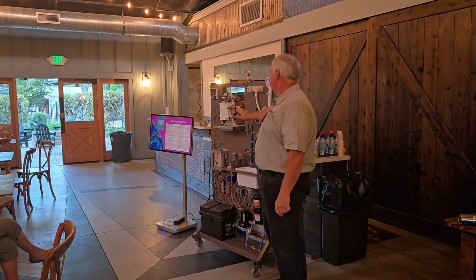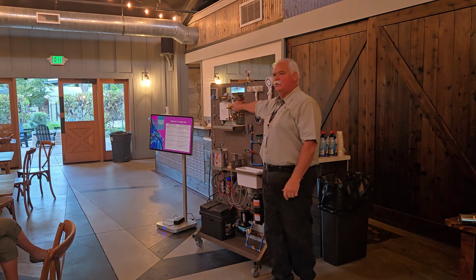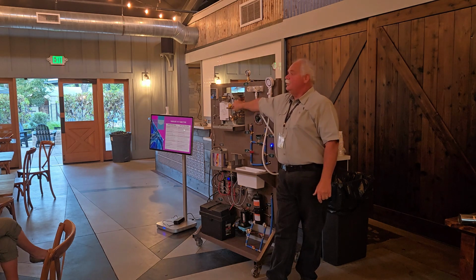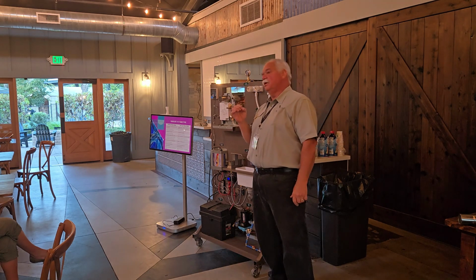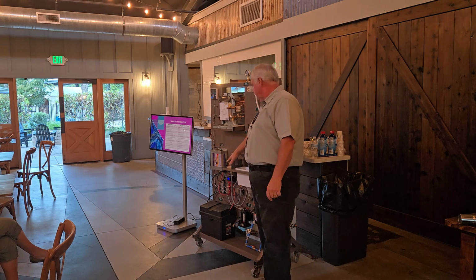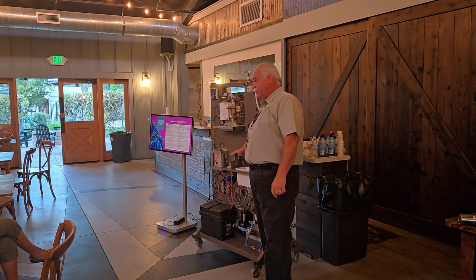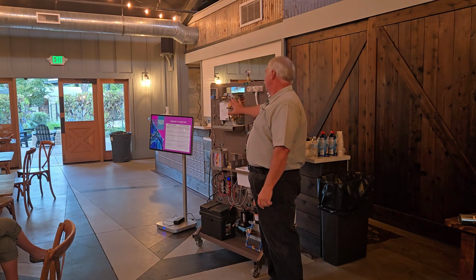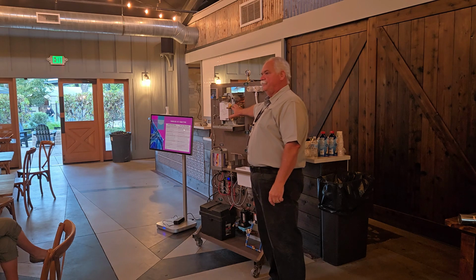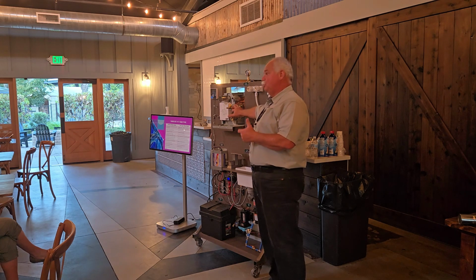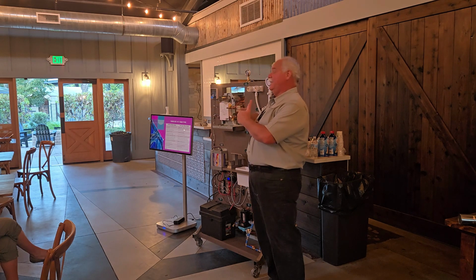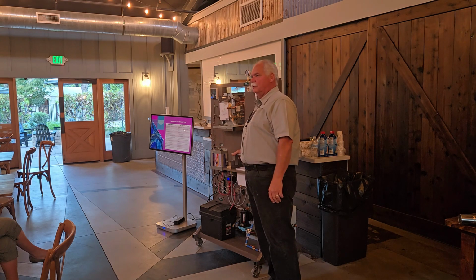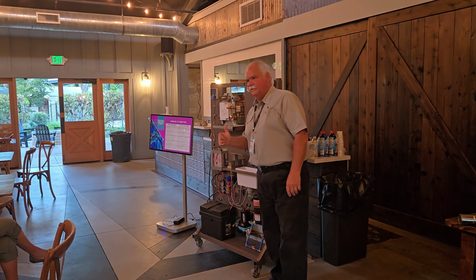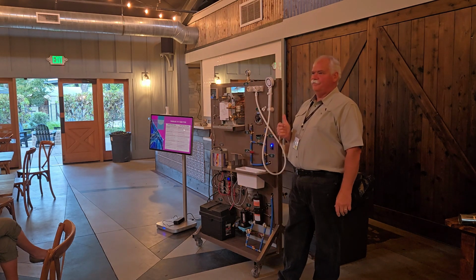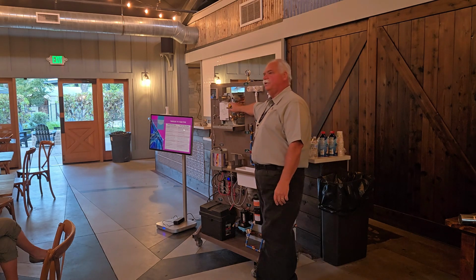What you're doing is further restricting water coming through this water heater because you only have so much volume coming in. So if I have the hot wide open and my cold open a little bit, I'm restricting what goes through here. It's going to make the problem worse. So you're going to have to keep opening that cold water. All of a sudden, you're going to freeze because you just dropped below 0.3 gallons per minute.